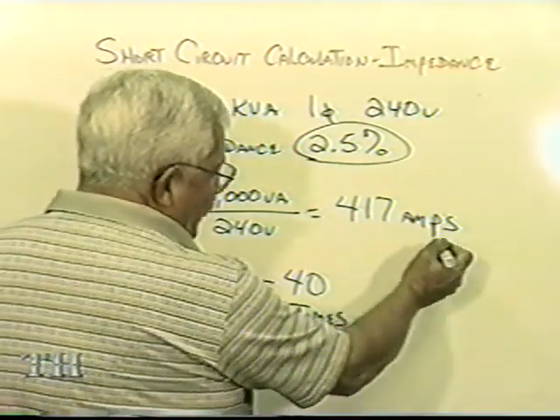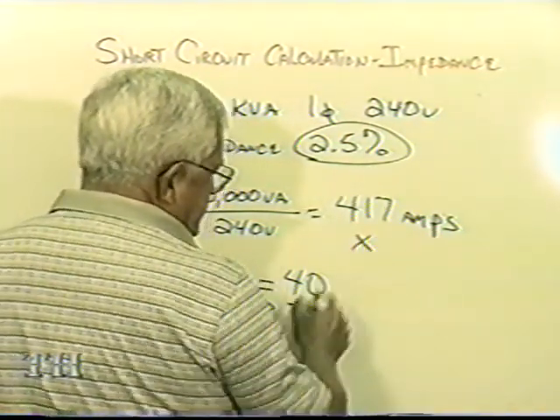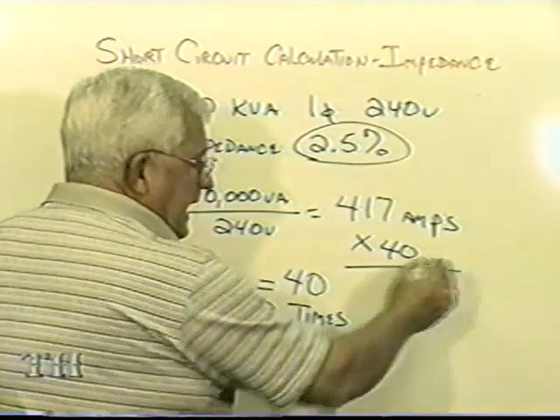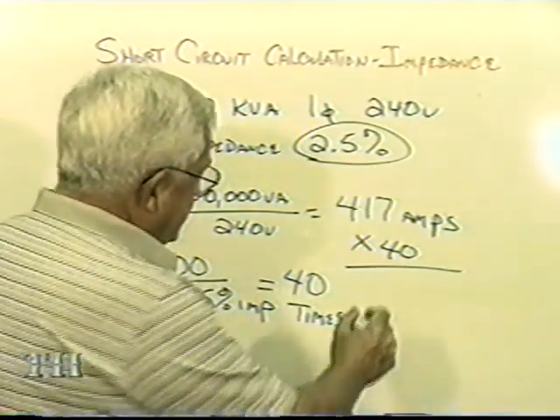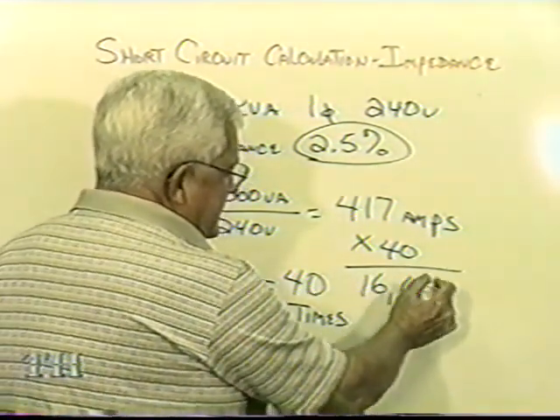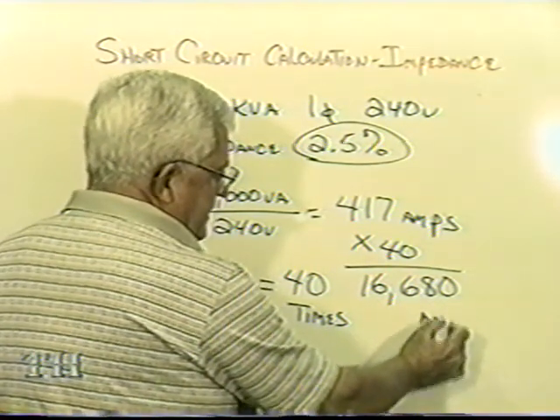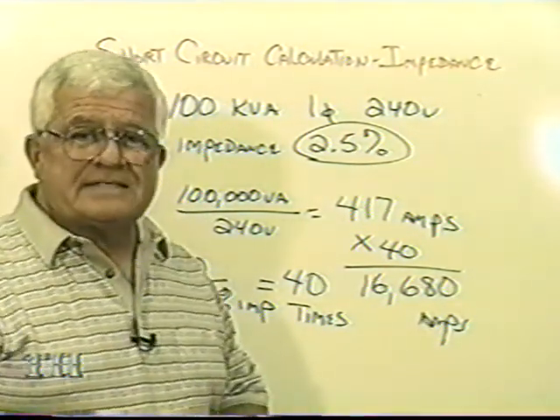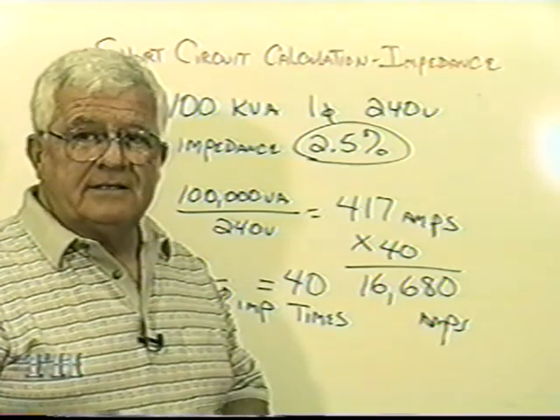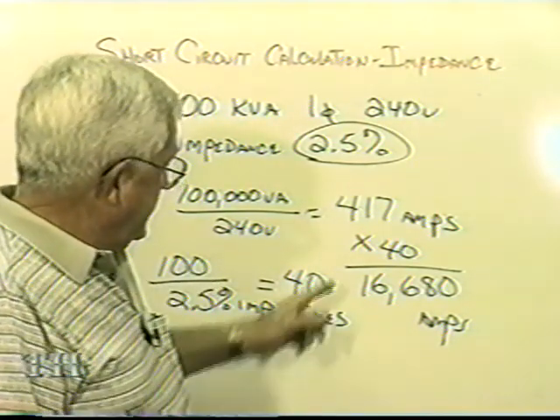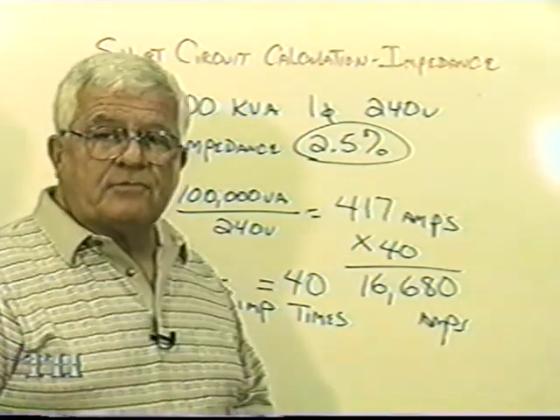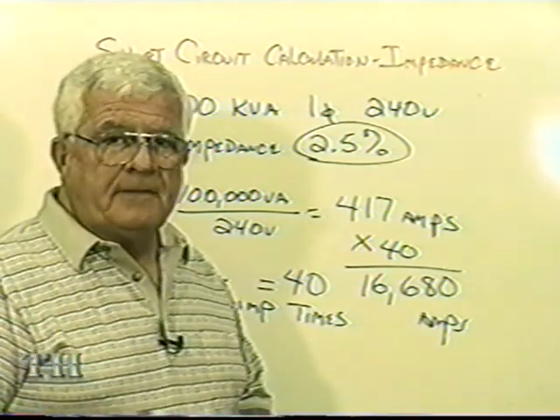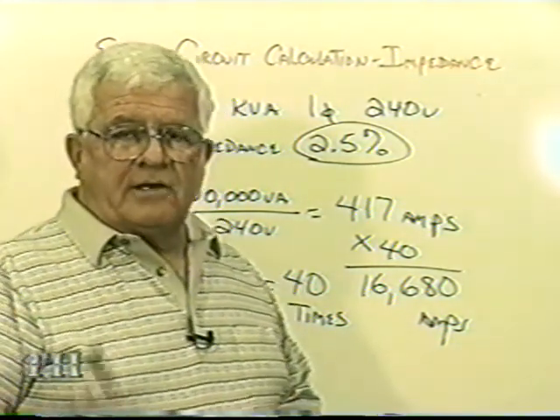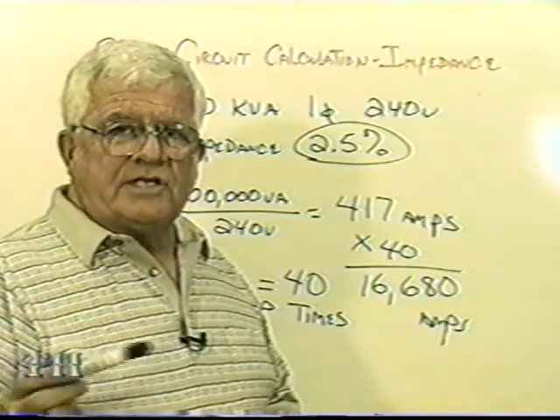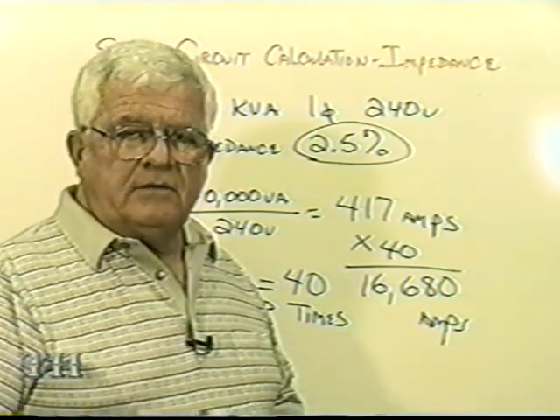So you take your rated current times 40. And the available short circuit here is like 16,680 amps. See, this thing increased 40 times, up to over 16,000 amps. Now give me a moment, I'm going to clear the board and I want to put a question on that's floating around right now on the examination.